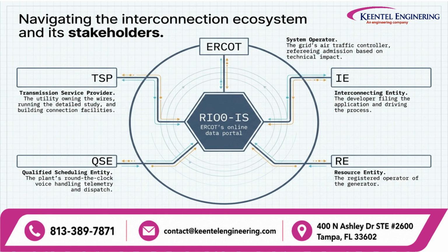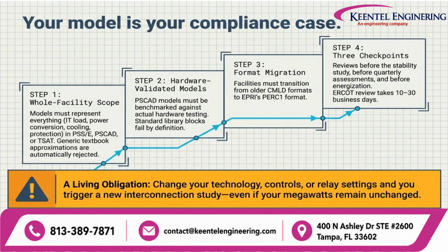The important point is that protection engineering must satisfy not only the physical requirements of the transformer, but also the technical, documentation, modeling, and compliance expectations of the wider interconnection process. In modern grid interconnection, your electrical model is effectively part of your compliance case. The first requirement is whole facility scope. Models must represent the actual facility, not just the generator. That means accounting for elements such as IT load, power conversion, cooling, protection, and other relevant electrical equipment.